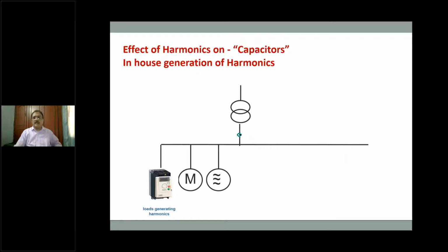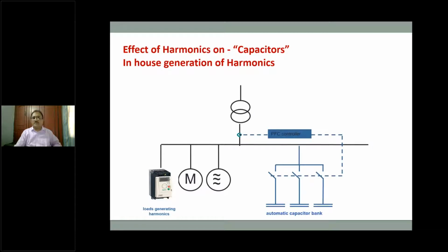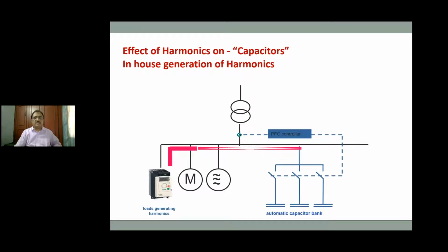And in a couple of slides I'm also discussing the effect of harmonics on capacitors, primarily because of resonance. Now, when you have a nonlinear load, harmonic is generated from the nonlinear load and it spreads to the parallel branch. This is a load which is generating harmonic. This is a normal motor, and this is a heating circuit, and there is a capacitor in the same branch. You find that the harmonic is not only going towards the grid, it is also spreading to the other branch circuits. This is a normal habit of a harmonic.